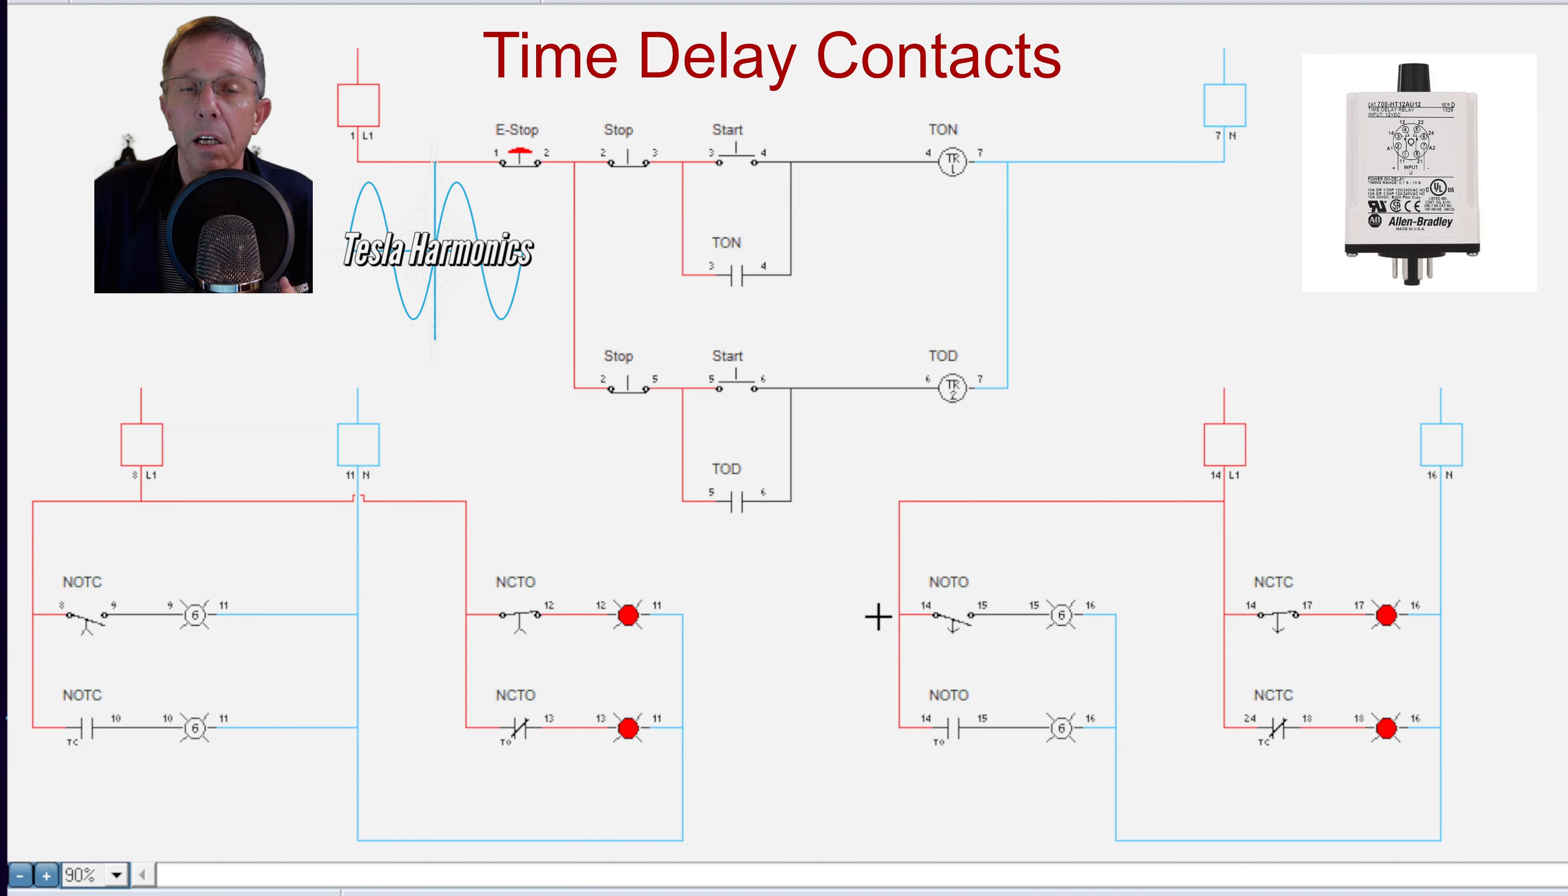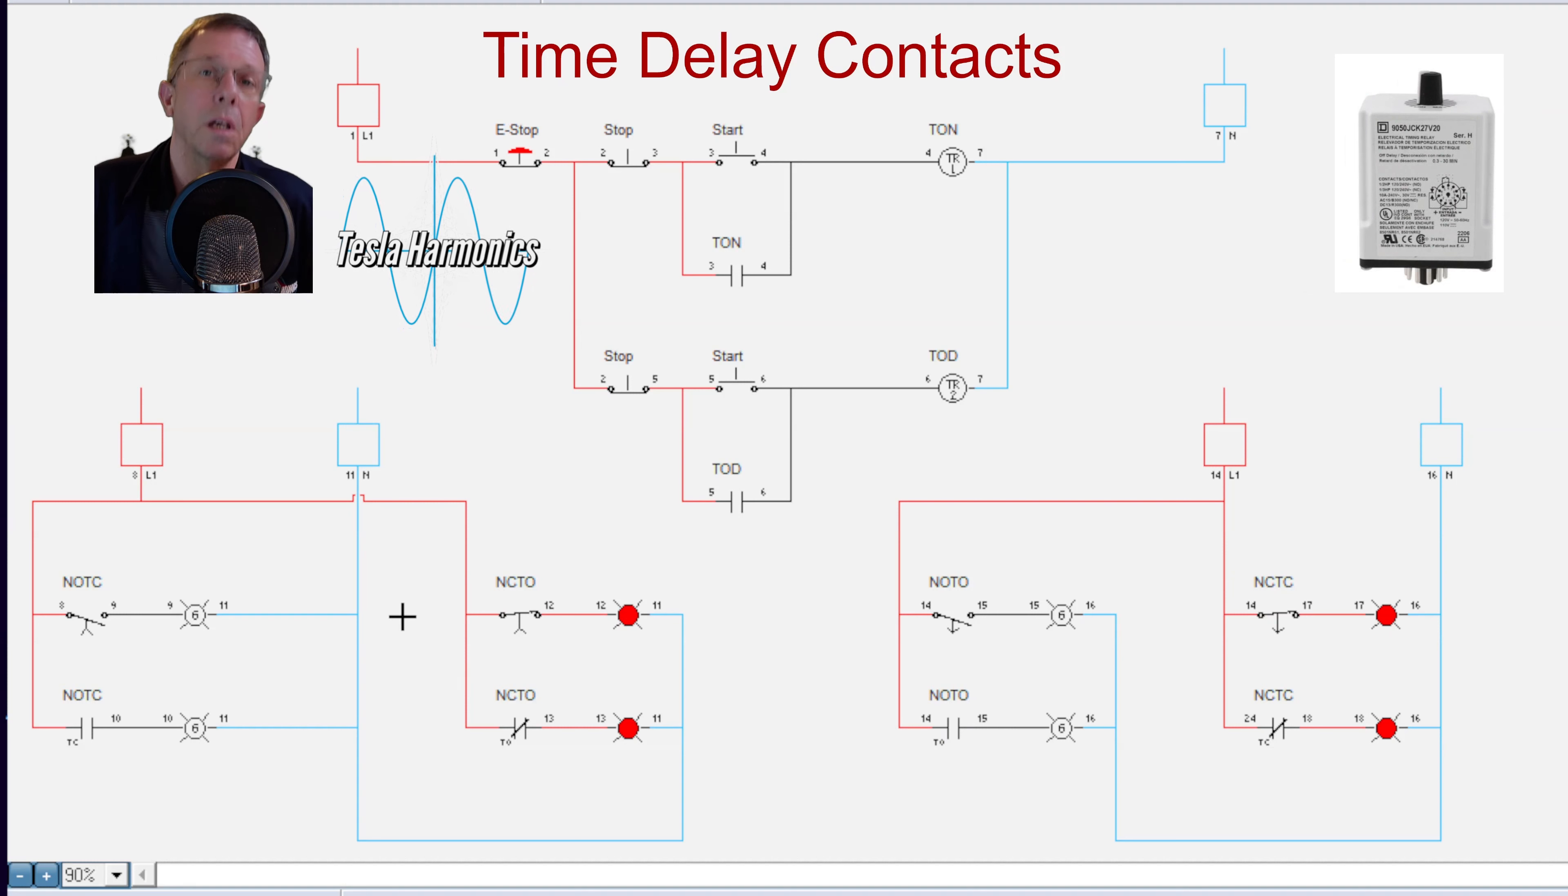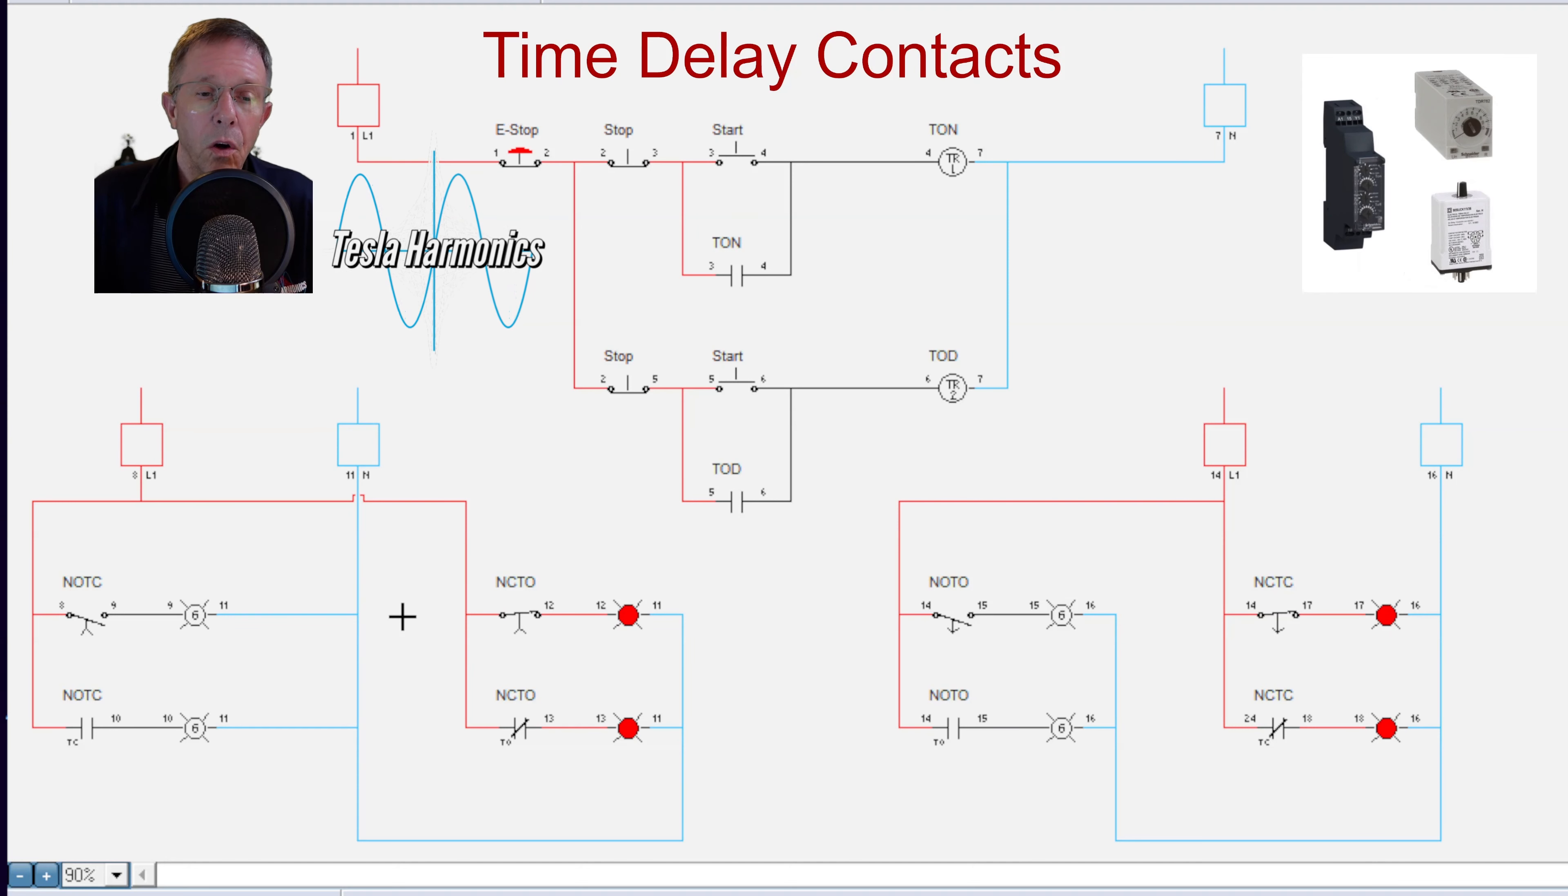Or I could use a normally closed and it would make it time open. So I can use an open contact on a time on delay and it delays the timing on like you would expect, but I can also use a normally closed and it would be energized at first while the timer is counting, and then when it's done counting it would go open.